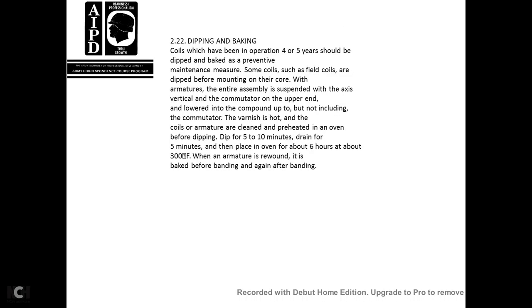222. Dipping and baking. Coils that have been operating 4 to 5 years should be dipped and baked as a preventive maintenance measure. Some of the coils, such as the fields, are dipped before mounting on their core. The armature, entire assembly, is suspended with the axis vertical, commutator upper end, and the lower end in the compound. The varnish is hot, and the coil armatures are cleaned and preheated in an oven before dipping. Dip for 5 to 10 minutes, drain for 5 minutes, then place in an oven for about 6 hours at about 300 degrees Fahrenheit.